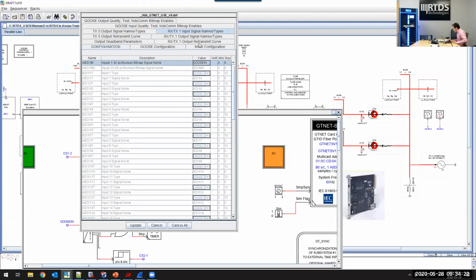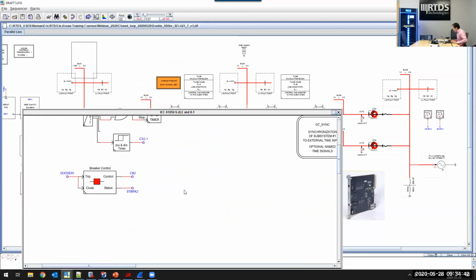Here we're in the input signal name menu tab. In this case, an integer variable named GooseIn is given to represent the Boolean input 1 to 32. Next step is to use this variable GooseIn to control breaker 2. To do that, the variable GooseIn is given to the 2 inputs of the breaker control component to eventually operate the target breaker.